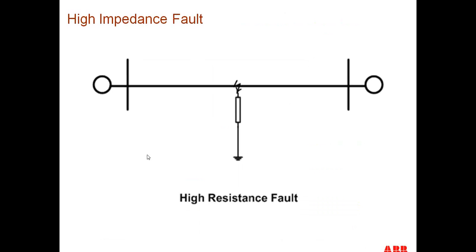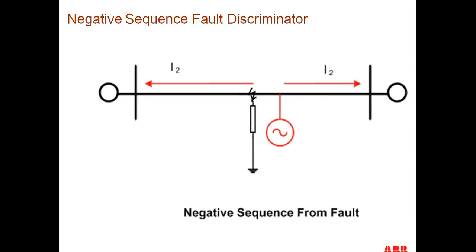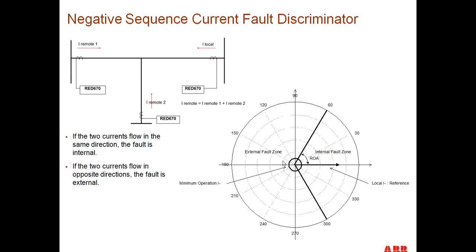Next, an area of concern is a high resistance fault. We want to be able to clear a high resistance fault, and the way we do that is using a negative sequence element. We know that negative sequence emanates from the point of the fault. So here we can see a negative sequence generator at the point of the fault that's pushing negative sequence current away from the fault. Then using our negative sequence differential element at each end of the line, we can determine whether or not there's a fault on the line.